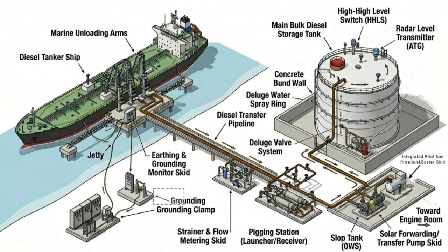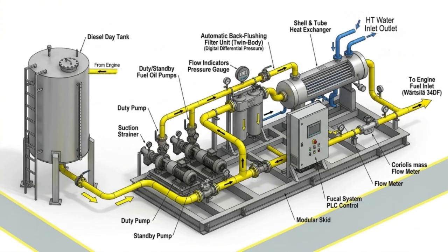With the primary gas path covered, let us now focus on the backup diesel system designed to ensure continuous power generation. Diesel fuel from the day tank enters the fuel conditioning skid, where redundant pumps maintain reliable fuel circulation, while automatic filtration systems remove contaminants continuously during operation. The fuel then passes through a shell and tube heat exchanger, utilizing the HT water circuit to maintain the required fuel temperature and viscosity before engine injection. Before reaching the engine, fuel consumption is monitored through a Coriolis mass flow meter, while the entire skid operation is automatically controlled by the local PLC system. This fully conditioned and continuously primed diesel line enables seamless transfer from gas mode to diesel mode whenever required.